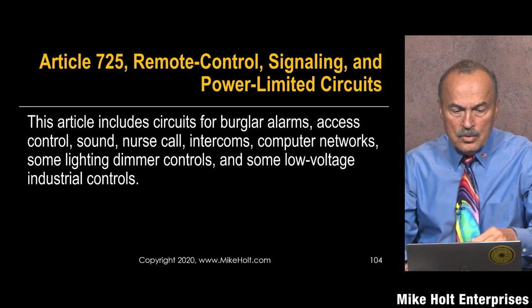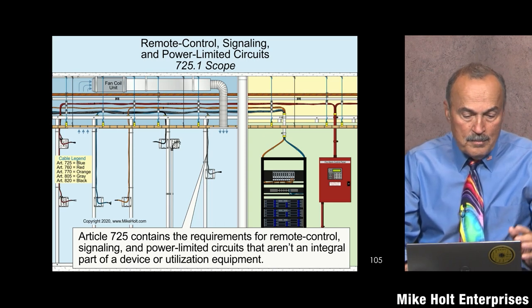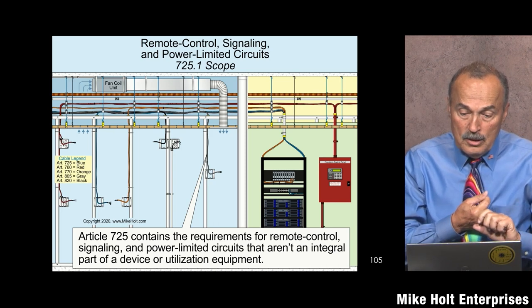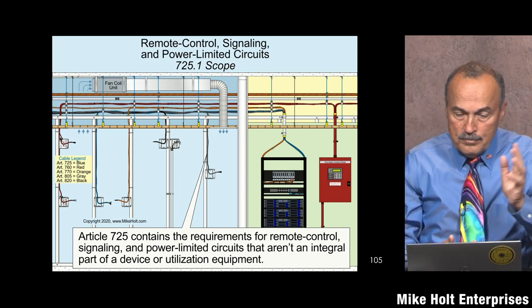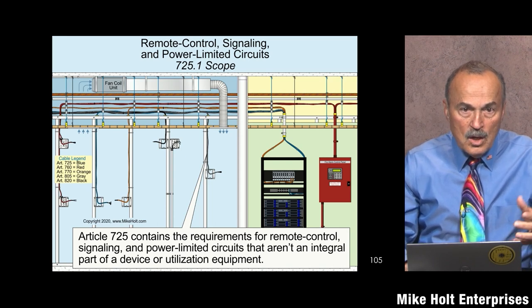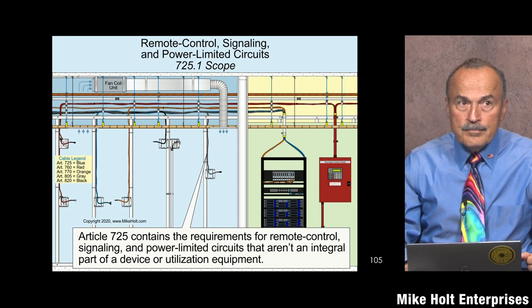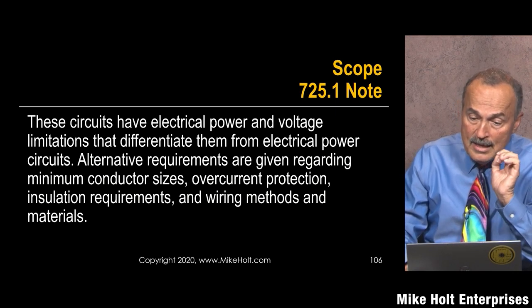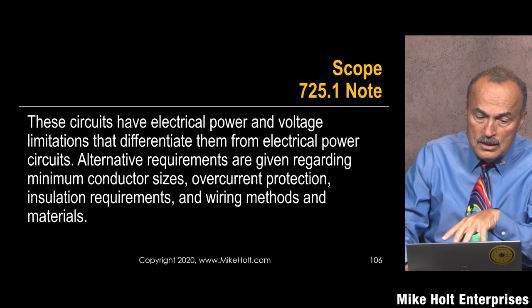I'm not going to get into burglar alarms, access control, nurse call, intercoms, computer networks, lighting dimming controls, or low voltage industrial controls. Article 725 contains the requirements for Class 1, Class 2, and Class 3 circuits that aren't an integral part of a device or utilization equipment. If something has its own internal wiring, that's covered under 110.2 and 90.7. These circuits have electrical power and voltage limitations that differentiate them from electrical power circuits, with alternative requirements for conductor size, overcurrent protection, installation, and wiring methods.